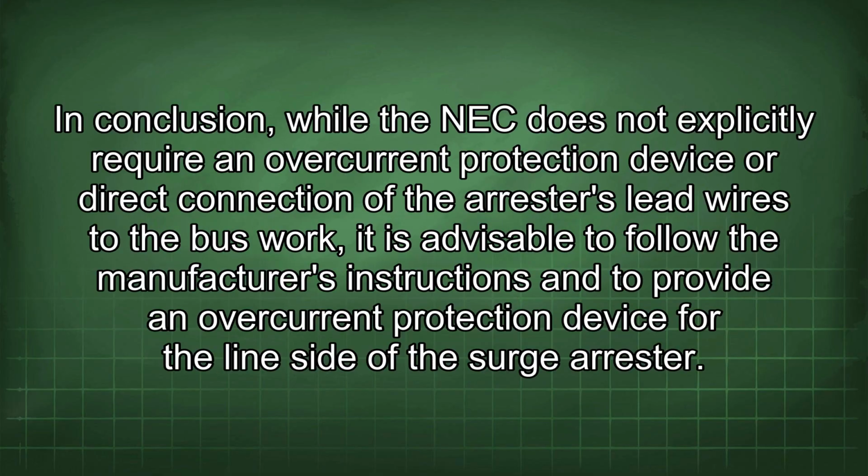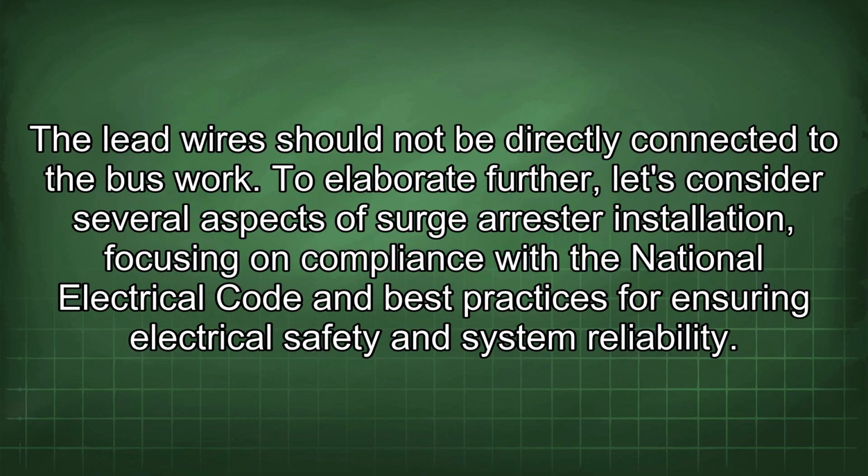In conclusion, while the NEC does not explicitly require an overcurrent protection device or direct connection of the arrestor's lead wires to the buswork, it is advisable to follow the manufacturer's instructions and to provide an overcurrent protection device for the line side of the surge arrestor. The lead wires should not be directly connected to the buswork. To elaborate further, let's consider several aspects of surge arrestor installation, focusing on compliance with the National Electrical Code and best practices for ensuring electrical safety and system reliability.